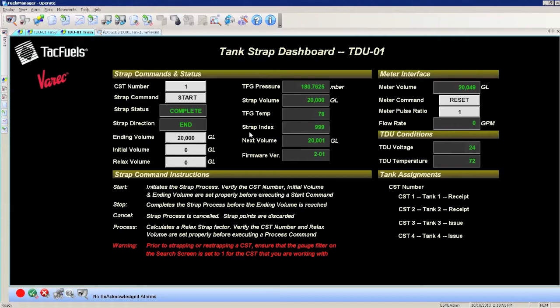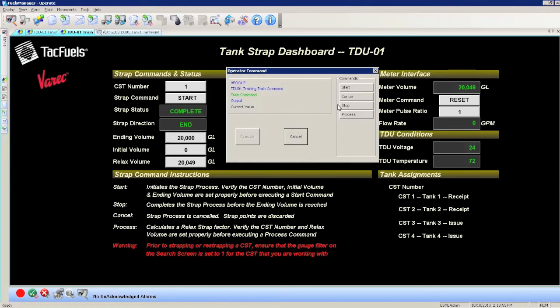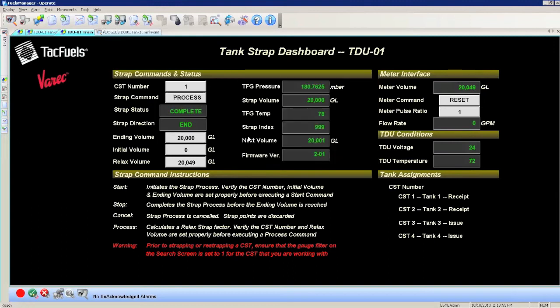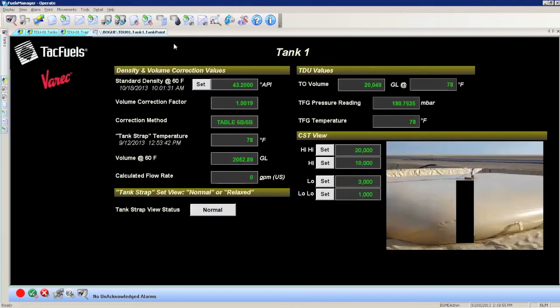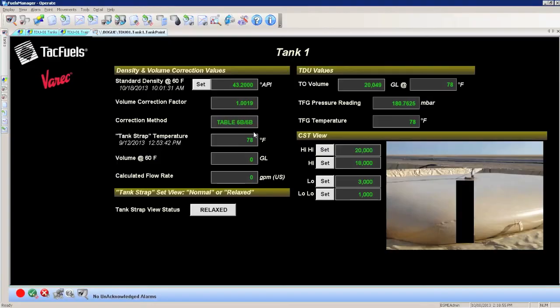You can identify when the resting period is over when no CST movement is detected by the gauge. From the operator interface tank mapping screen, ensure the CST number corresponds to the tank ID. Enter the final meter volume amount into the relaxed volume field and process the change using the strap command button. This will set the relaxed strap that will be used for all future measurements from the CST. Lastly, in the tank detail screen, change the tank strap view status to relaxed. This completes the tank mapping process.